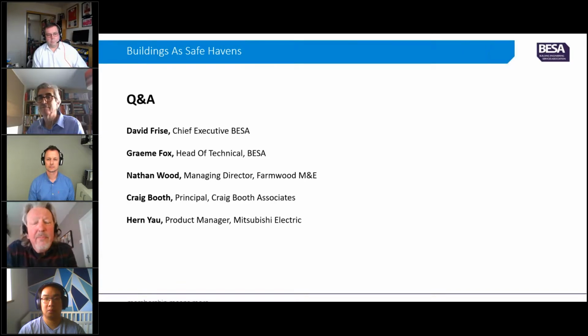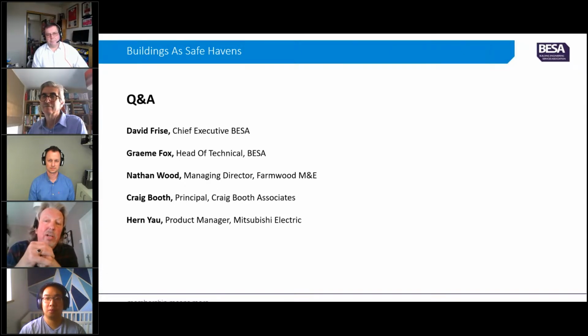I look at MVHR, mechanical ventilation with heat recovery systems, going into domestic dwelling units and flat blocks, and it's horrendous. We're building sort of vertical slums with horribly installed MVHR systems, with 6 meters, 8 meters of flex ductwork squashed into inappropriate spaces, which means that's certainly going to add to the noise. The poor old manufacturer of the MVHR fan system gets blamed for a noisy system, but you've got this horrible tortuous flex duct run which is horribly noisy, and that might well lead the occupant to switch off the MVHR for being noisy.